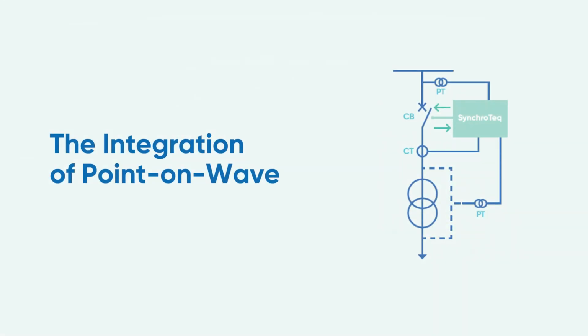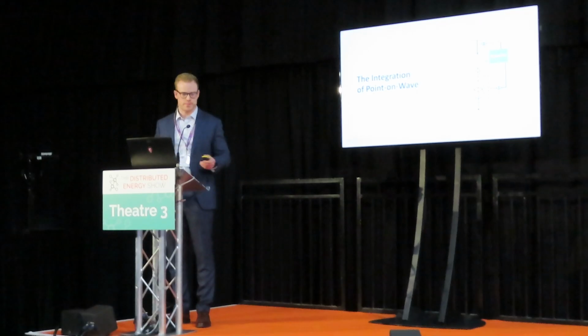The integration is pretty simple. You've got your transformer, you've got a number of VTs and CTs, you've got a synchronizing VT so it can see the phase angle of the grid and control when it's going to switch the circuit breaker, and then it's got a downstream PT, and that's what it's using to actually watch the transformer de-energization and calculate the residual flux.